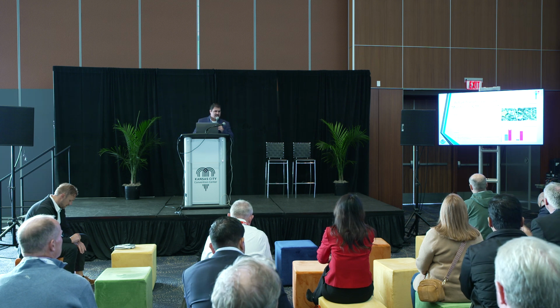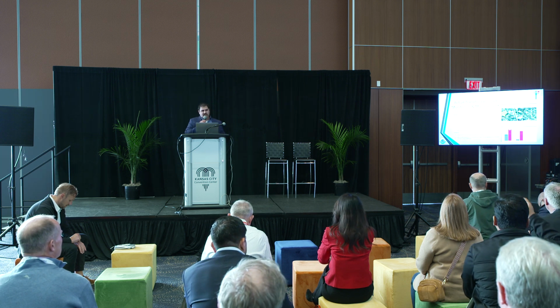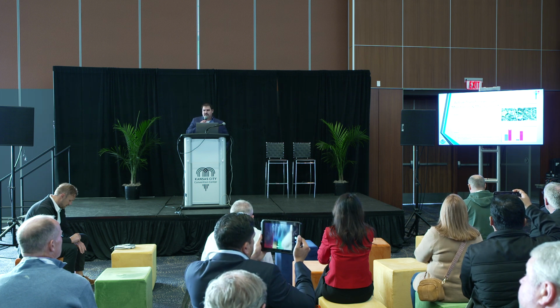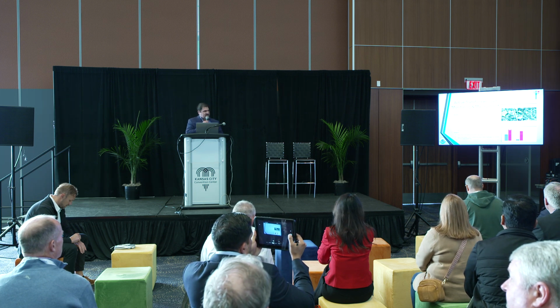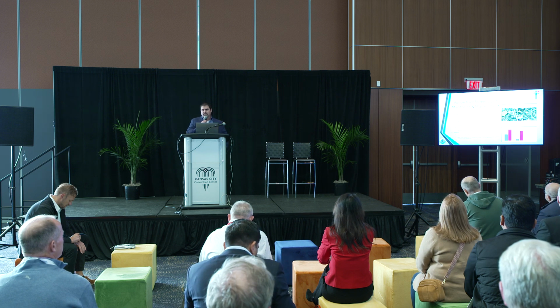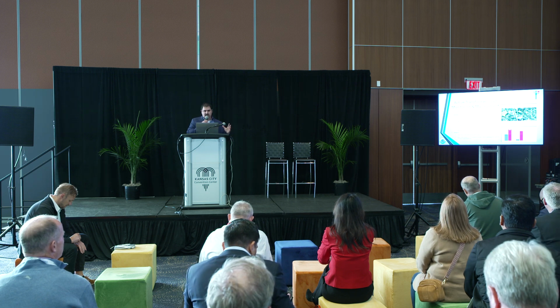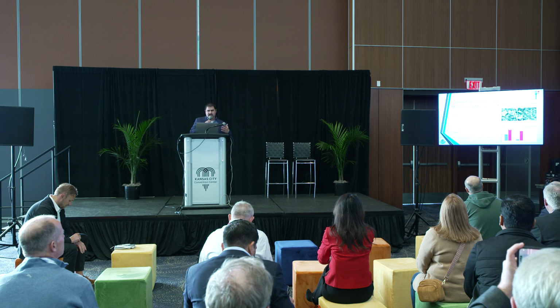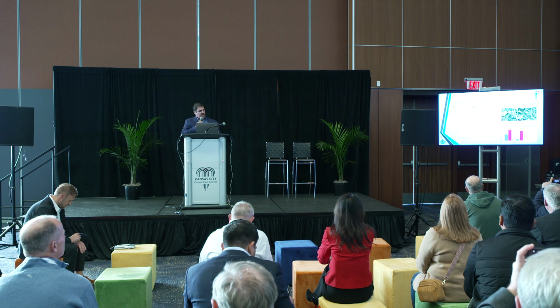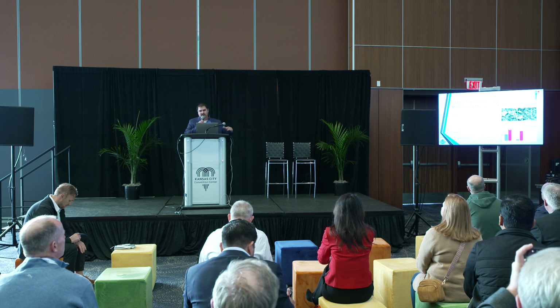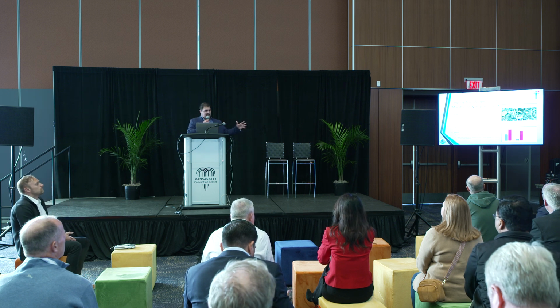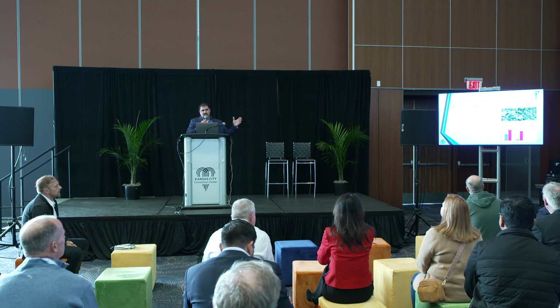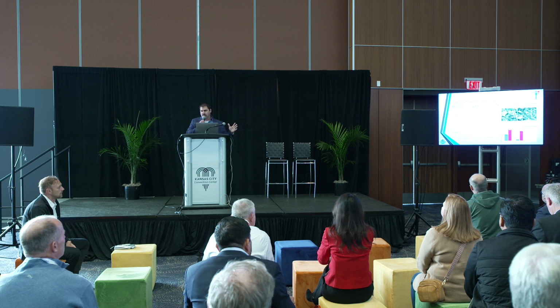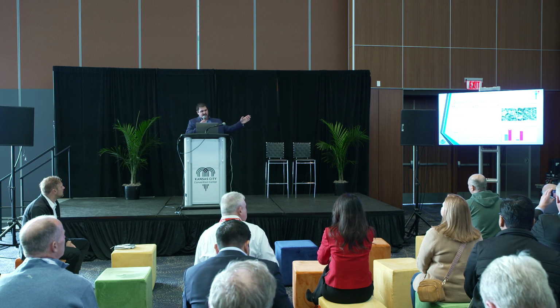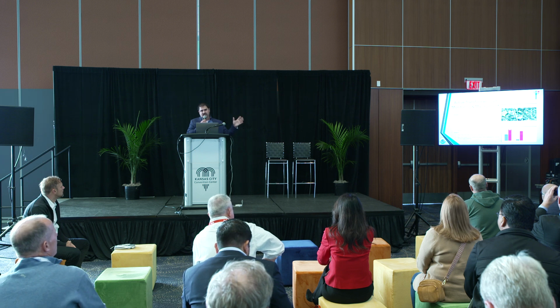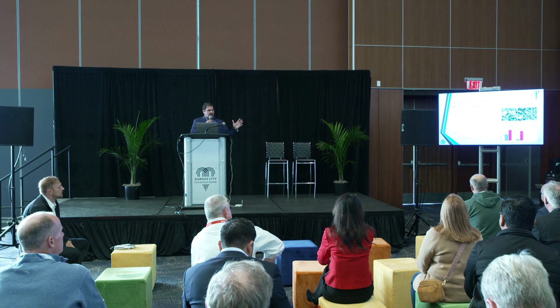So now that you know how things are electrically connected, clearly when we start to think about the impact of various loads or new loads on the distribution assets, aggregating that loading to the core piece of distribution equipment that doesn't have visibility is foundationally the distribution transformer. So you have eyes on your reclosers, you have eyes on your cap banks, your feeder heads at the substation, but foundationally where the biggest change in load from a bidirectional load flow and impacts from an EV standpoint is effectively the distribution transformer.